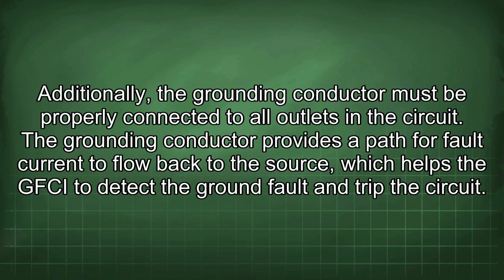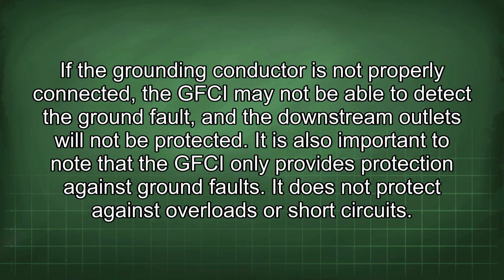Additionally, the grounding conductor must be properly connected to all outlets in the circuit. The grounding conductor provides a path for fault current to flow back to the source, which helps the GFCI to detect the ground fault and trip the circuit. If the grounding conductor is not properly connected, the GFCI may not be able to detect the ground fault, and the downstream outlets will not be protected.